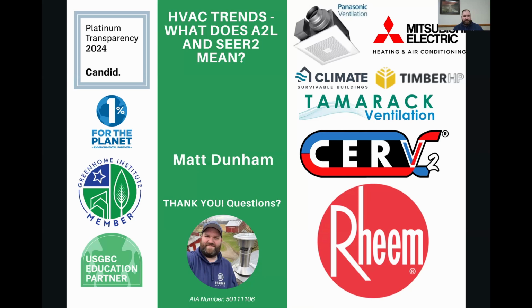The biggest one: Consumers Energy here in Michigan wants you taking supply air and return air enthalpies, and they want you calculating your enthalpy per pound removed, because the manufacturer designed for 6.4 BTUs per pound of air. And they expect you to be within 85% of that.